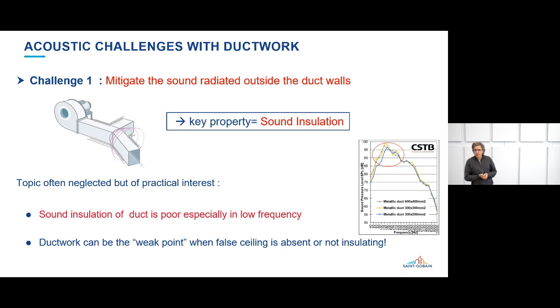You have an example, a curve on the right, giving you the sound pressure level measured for different metallic duct sections, from 300 by 400 to 600 by 400 square millimeters. So, the sound level radiated versus frequency. What you can observe is that typically from 50 to 500 hertz, the sound level is very high. This means that the sound insulation of rectangular ductwork is very low in low frequency. So it can be the weak point in practice.